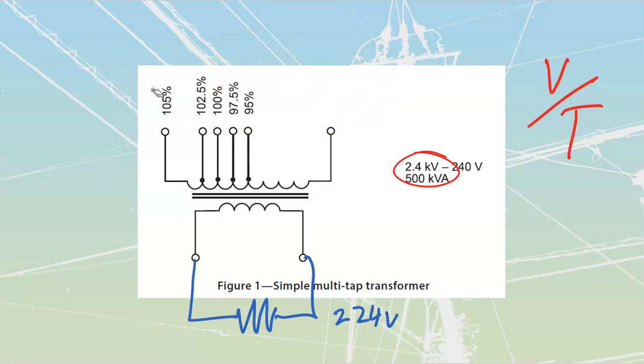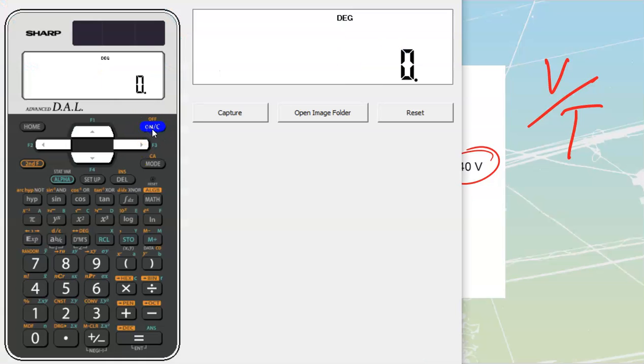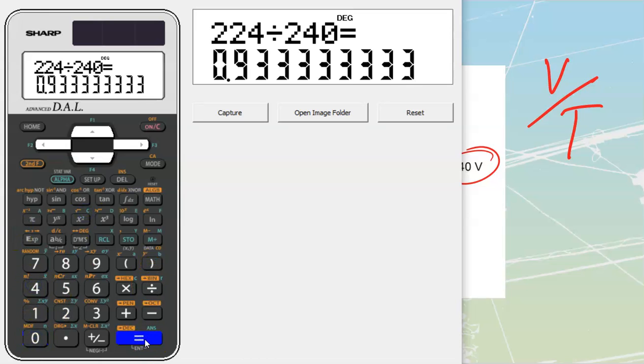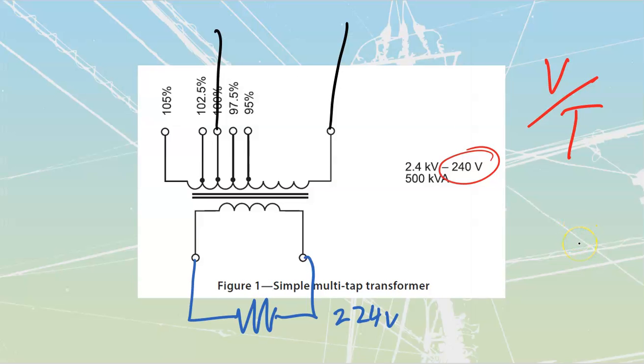Instead, I'm going to be looking at this low voltage side. And I see over here it's 224 volts, and I see that I've got a rating of 240. So what I'm going to do is just take a percentage out of here. We'll take 224, my actual amount, out of my rated 240, which gets me to a value of 93%.